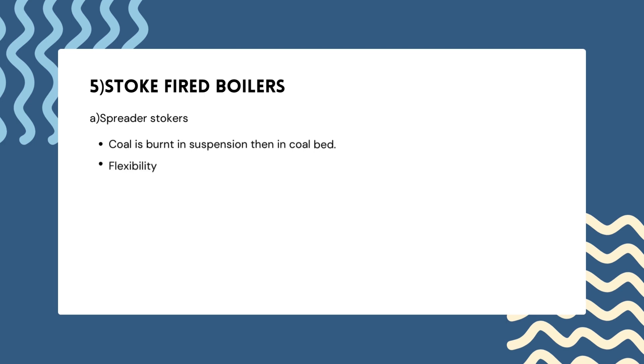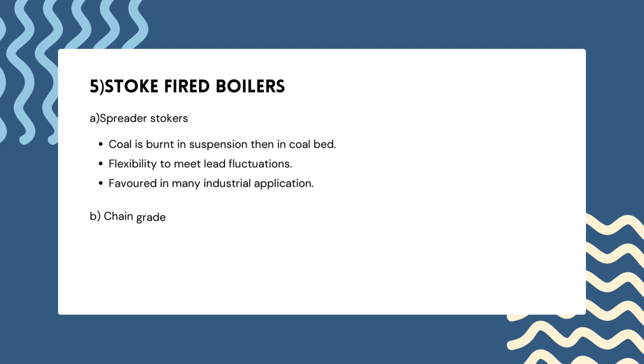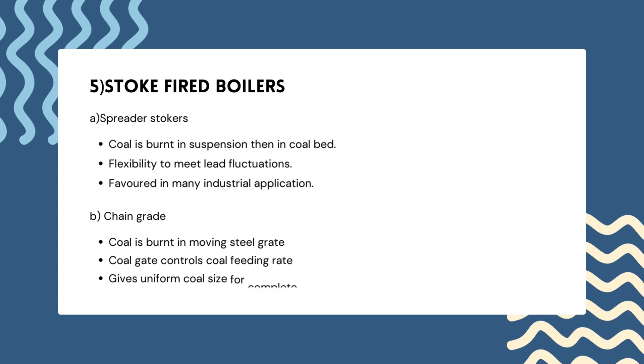Stoker fired boilers include two types. The first is the spreader stoker, where coal is first burned in suspension and then in the coal bed, offering flexibility to meet fluctuations and used in both suspension and grate burning. The second is the chain grate or travelling grate stoker, where coal is burned in a moving steel grate. A coal gate controls the coal feeding rate, giving uniform coal size for complete combustion.